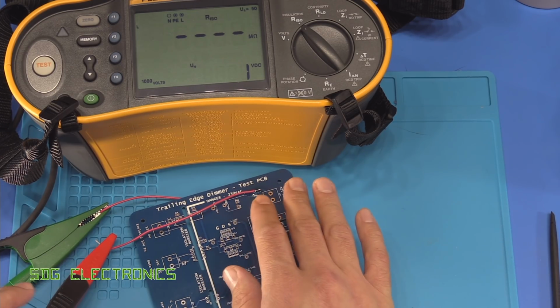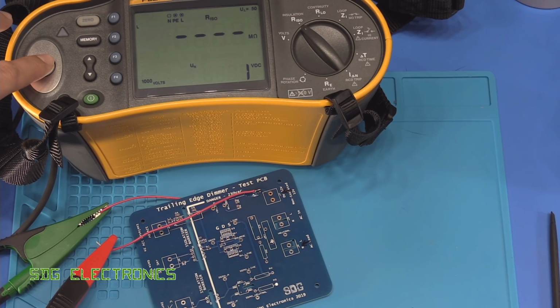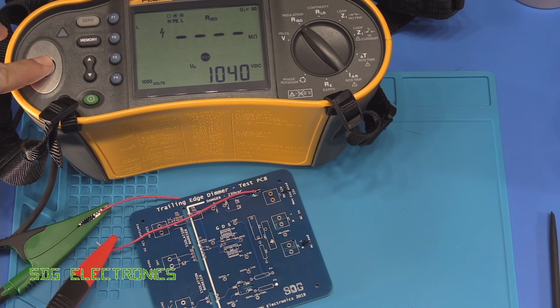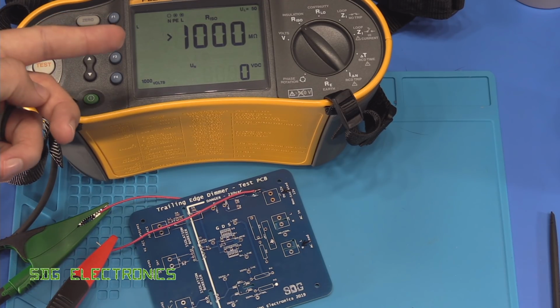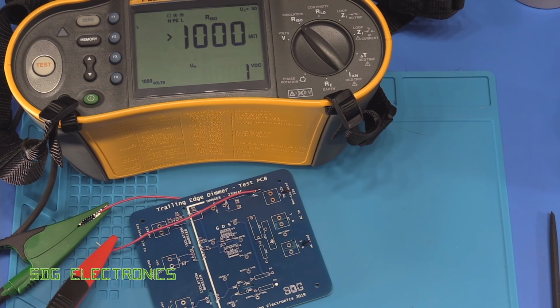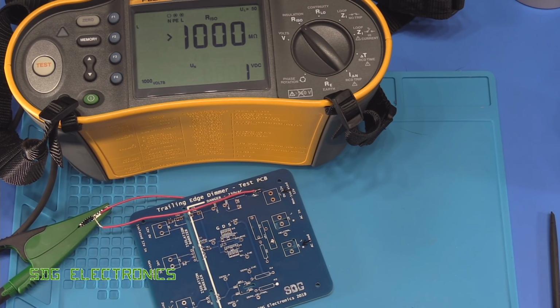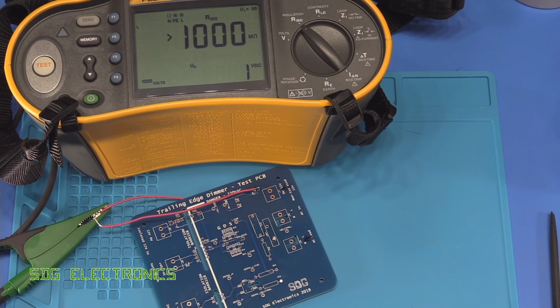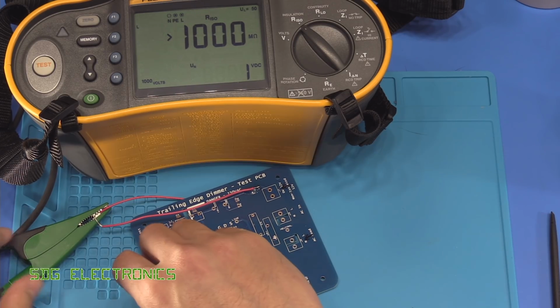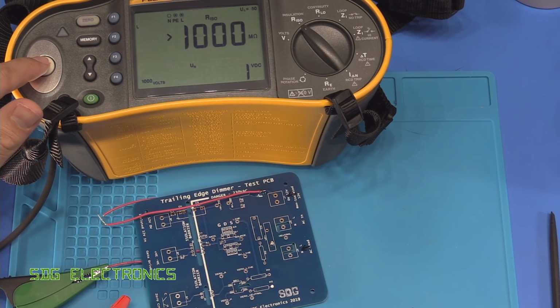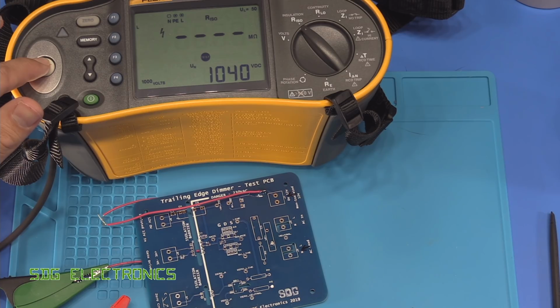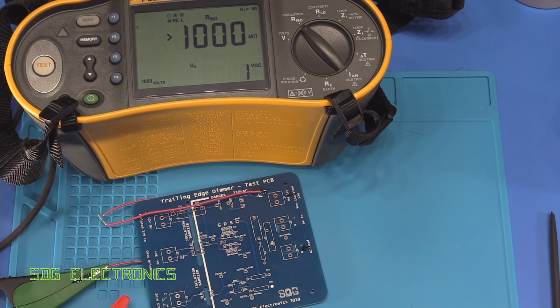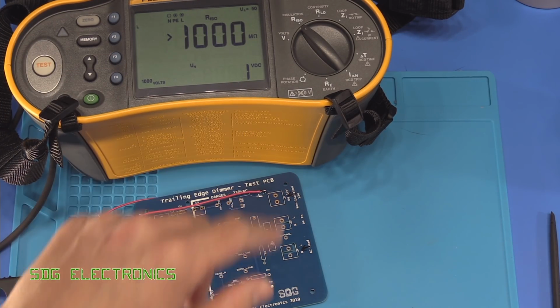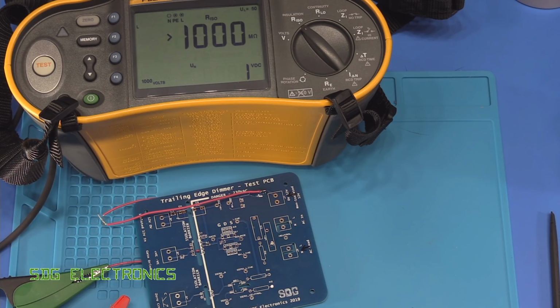But anyway, we've got this hooked up now, and if we press the test button, it will test it at 1000 volts. And you can see we've got greater than 1 gigohm of impedance. We'll just check the one with the slot as well, but we should have the same figure here. This should just give us a reference point. And we'll press test again. And there we go. So greater than a gigohm with 1000 volts being tested.